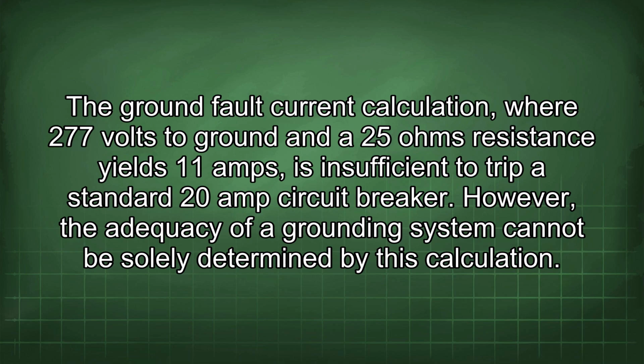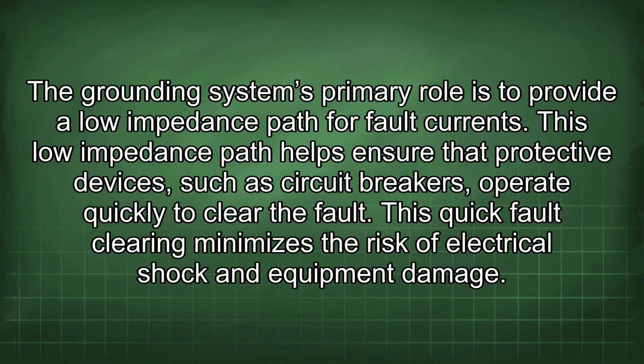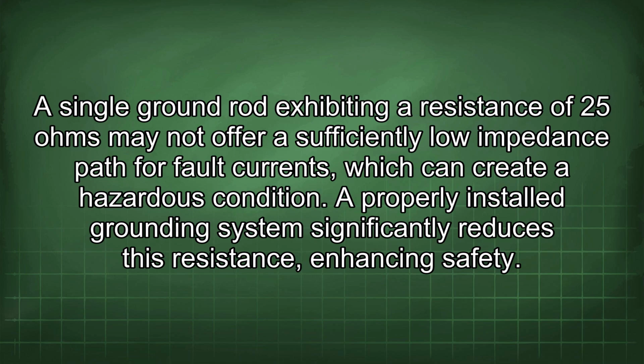However, the adequacy of a grounding system cannot be solely determined by this calculation. The grounding system's primary role is to provide a low impedance path for fault currents. This low impedance path helps ensure that protective devices, such as circuit breakers, operate quickly to clear the fault. This quick fault clearing minimizes the risk of electrical shock and equipment damage. A single ground rod exhibiting a resistance of 25 ohms may not offer a sufficiently low impedance path for fault currents, which can create a hazardous condition. A properly installed grounding system significantly reduces this resistance, enhancing safety.